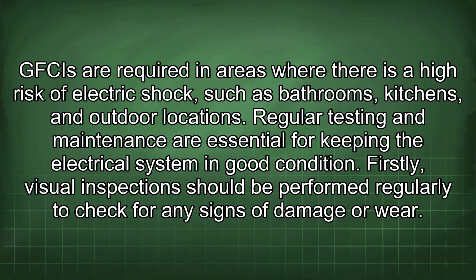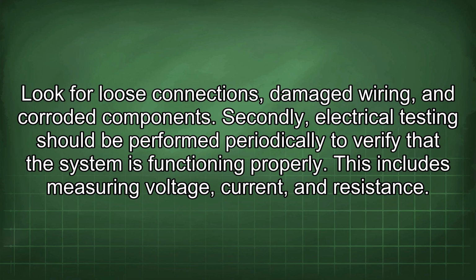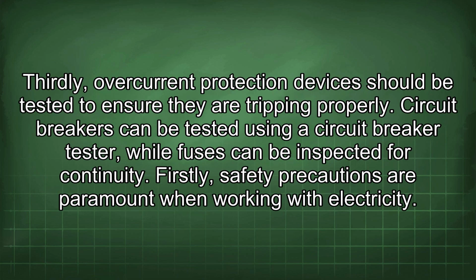Firstly, visual inspection should be performed regularly to check for any signs of damage or wear. Look for loose connections, damaged wiring, and corroded components. Secondly, electrical testing should be performed periodically to verify that the system is functioning properly. This includes measuring voltage, current, and resistance. Thirdly, overcurrent protection devices should be tested to ensure they are tripping properly. Circuit breakers can be tested using a circuit breaker tester, while fuses can be inspected for continuity.